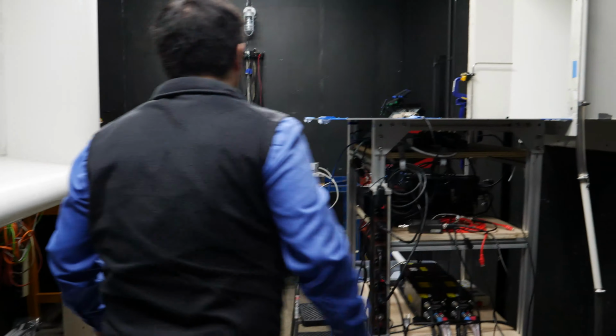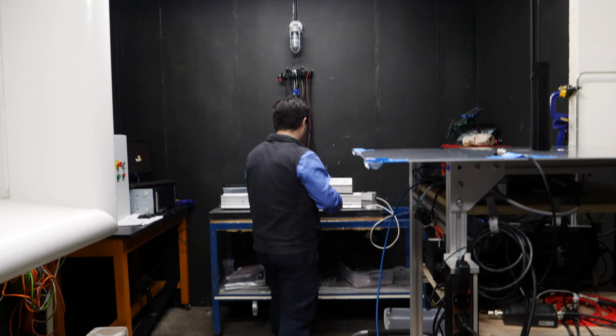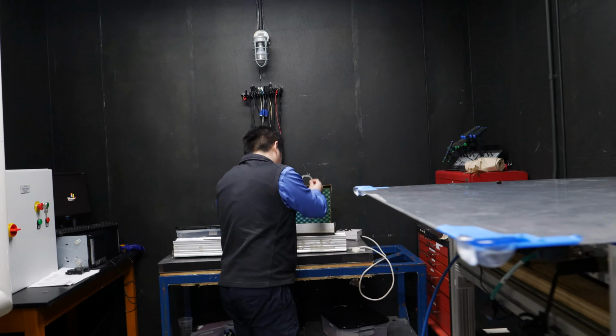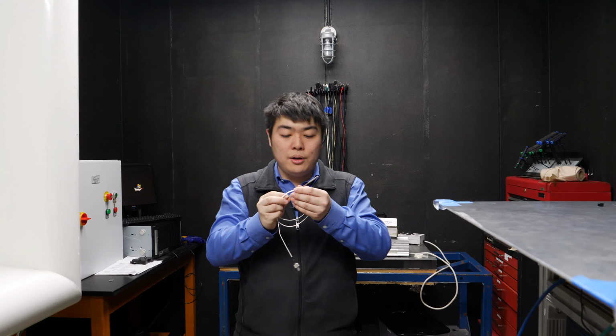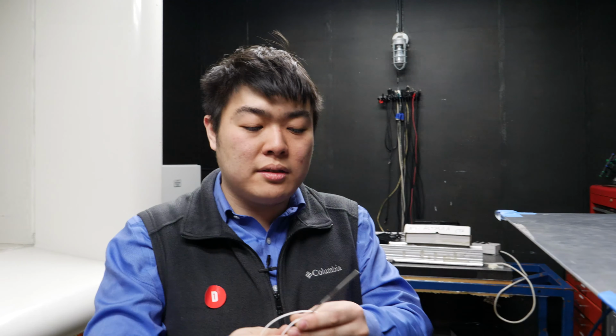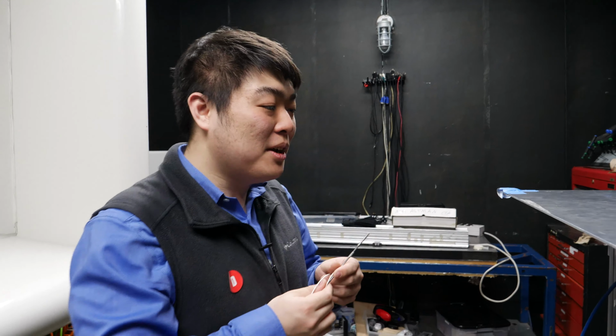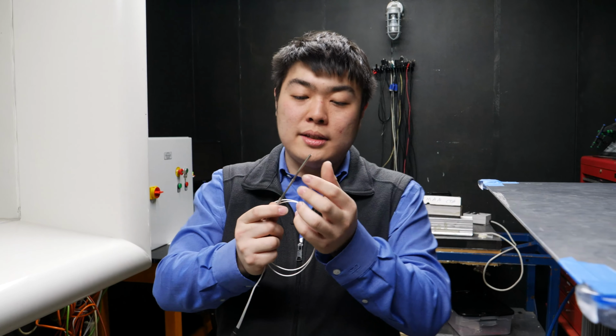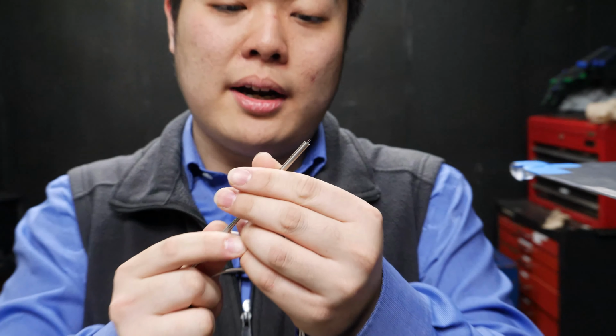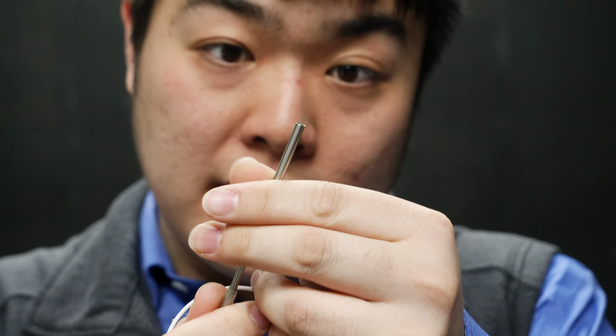So then we're gonna take our hot wire sensor, which is here. So the hot wire sensor is very vulnerable, so it can break very easily. So if you move this cover down, you will see the hot wire coming out. So there is the hot wire. So whenever you're not using the hot wire, measuring the flow velocity or doing an experiment, do not expose the hot wire in the free stream or the air, because it will break very easily.